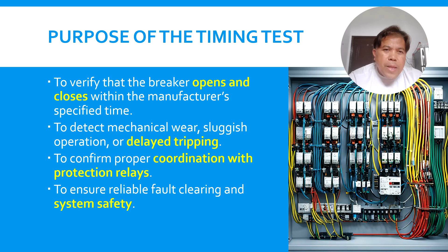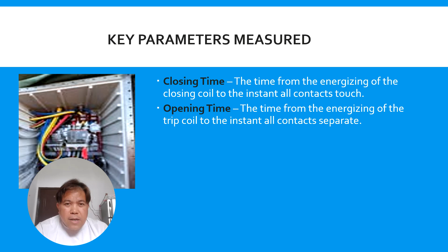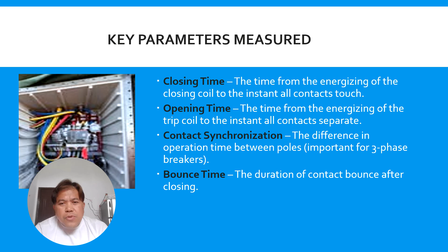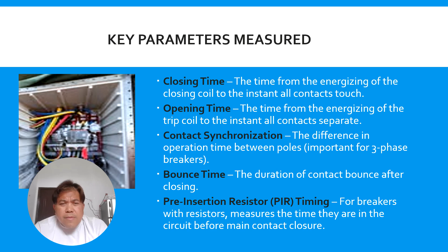So now we understand how important the timing of our circuit breaker is. Now we'll proceed to the parameters. What are the parameters to be measured? First, you have to measure the closing time. Next, you have to measure the opening time, because we have a coil and a contact in the breaker. When you open the breaker itself, there is a small coil in combination with our contact. We also have the timing and contact synchronization, which is important for a three-phase breaker, and then the bounce duration of the closing. The other one is the pre-insertion resistor, for breaker timing with resistors. These are the basic parameters that we are measuring.